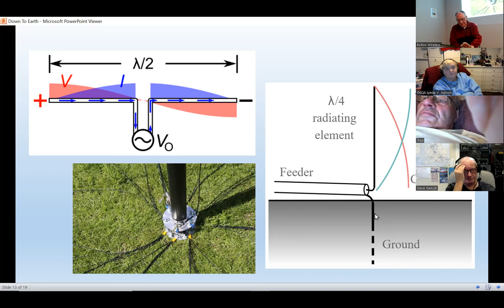This is why you really want a single ground point in your station. If you're going to earth things, use a single ground point. Bring your earth cable into your station to some sort of great big block if you can, and just connect individual cables from everything you want to ground to that ground point. Then you'll avoid the situation as up above there.